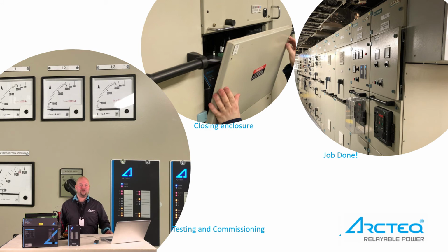Testing and commissioning. Push the button, 3 seconds, 3 seconds. Check no error lights. All the inputs are connected, all the dip switches are connected, thresholds are correct. Then test kit injects the current, flash with the camera flash or with the test kit flash. Close the enclosure and then change this commissioning switch position back to ready mode, then the job is done.